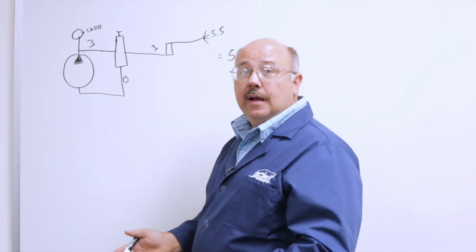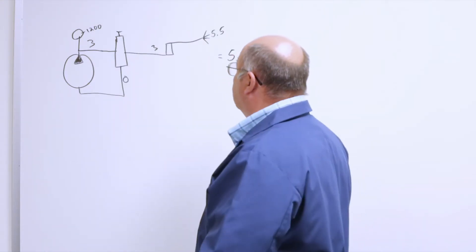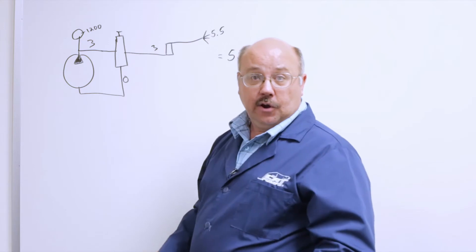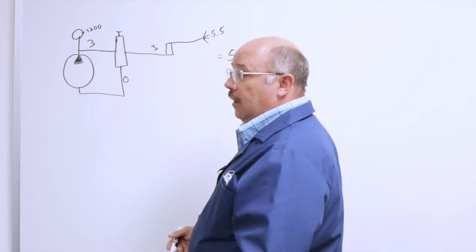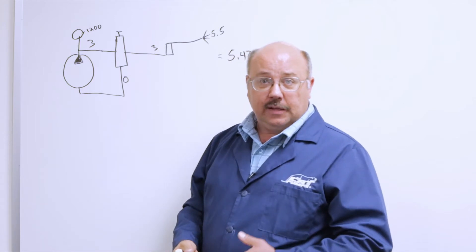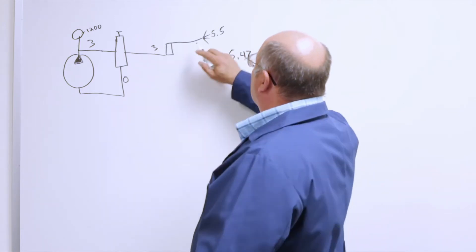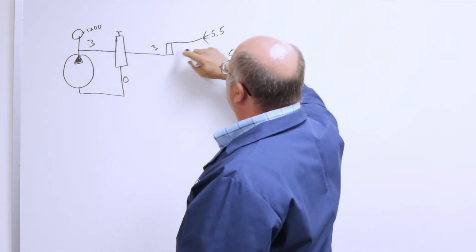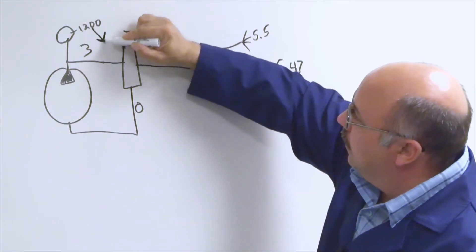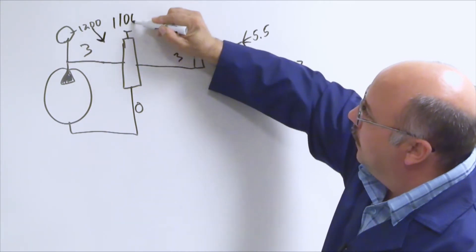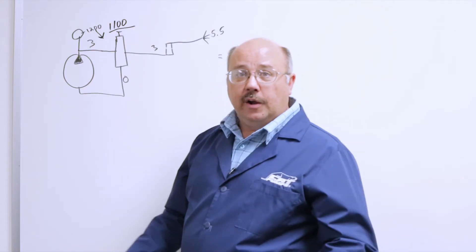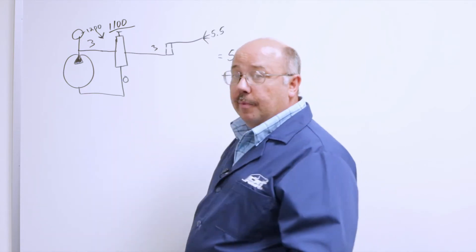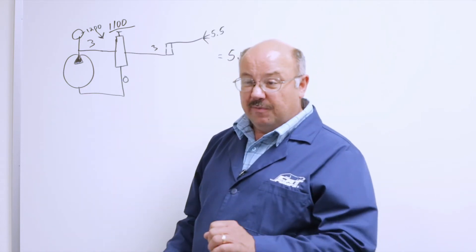As we shut the gun off, the three gallons will go to bypass. Then when we reopen the trigger gun we'll reinitiate our three gallons a minute out the tip at 1,200 psi. Now what happens over time, maybe a couple years or a few thousand hours, this nozzle is going to wear. When it wears, the hole gets larger, and the pressure will drop because we still have the same flow. So let's say this got larger and now the pressure is going to drop to maybe 1,100 psi. So we've lost pressure in the system not because the pump has worn out, not because the unloader's bad, but because the nozzle has worn, which is very hard to see.